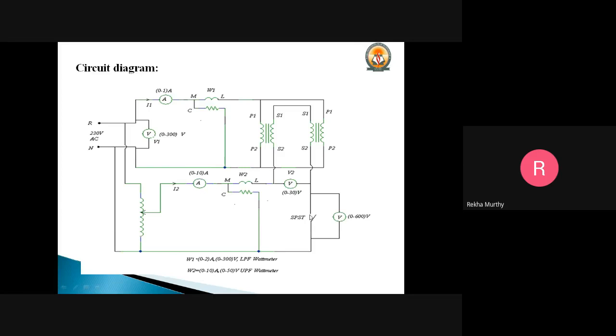So here, with the SPST switch kept open, make sure the auto transformer is in the minimum position and the supply is switched on. Okay, right. Then the polarities of the secondary voltages of the transformers will be checked by making use of the voltmeter which is connected across the SPST switch. I hope you can see that this voltmeter, which has a range of 0 to 600, is just to check the polarities of the secondary voltages. Okay, fine. How to check that?